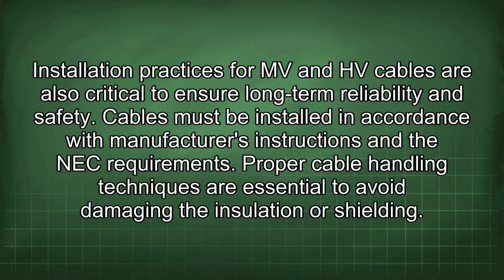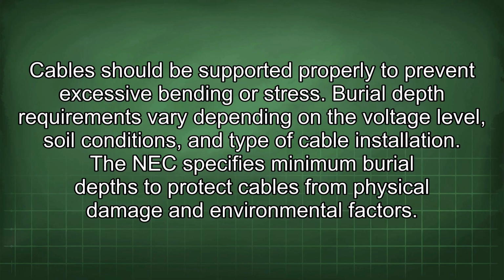Installation practices for MV and HV cables are also critical to ensure long-term reliability and safety. Cables must be installed in accordance with manufacturer's instructions and the NEC requirements. Proper cable handling techniques are essential to avoid damaging the insulation or shielding. Cables should be supported properly to prevent excessive bending or stress. Burial depth requirements vary depending on the voltage level, soil conditions, and type of cable installation. The NEC specifies minimum burial depths to protect cables from physical damage and environmental factors.